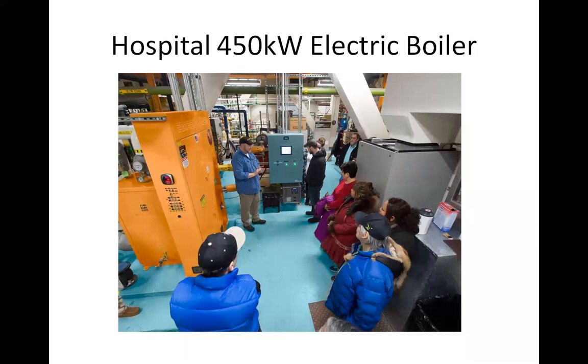The gray box with the touch screen in the middle and the 2 green lights is our remote control panel. That control panel was installed by us, Kotzebue Electric, and we're tied to it via wireless link. Inside it is a small PLC that operates the heating elements, which are in the orange box on the left side — that's the actual electric boiler.